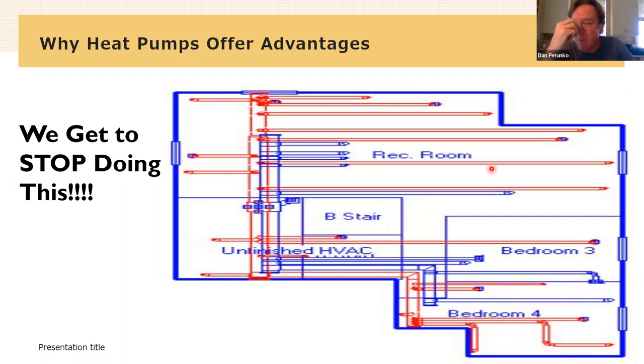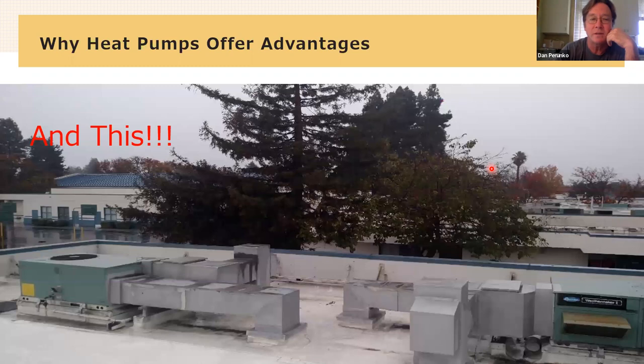And that comment comes from the fact that there's two things we have to think about. One is efficiency of the machine, and one is the efficiency of the delivery system. And even if these ducts were relatively tight and reasonably well insulated, they're so freaking huge that they're losing capacity based on having too much surface area, right? So what we really want to do is compact systems. We want to move away from giant systems like this, right?